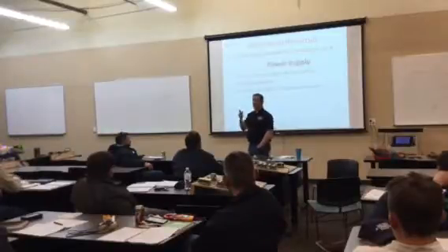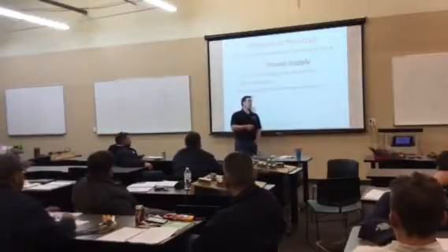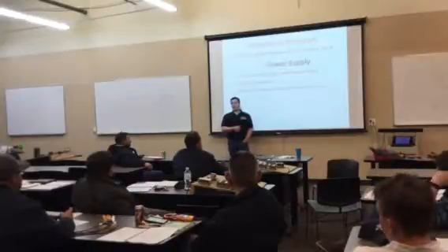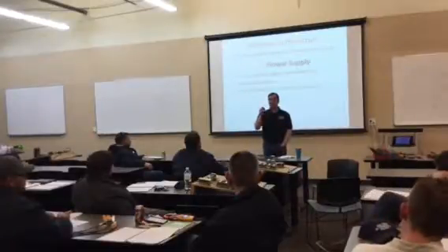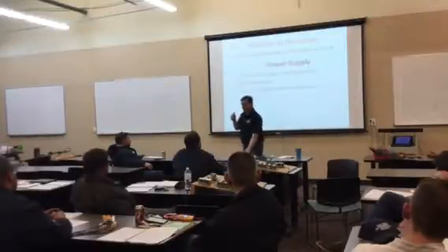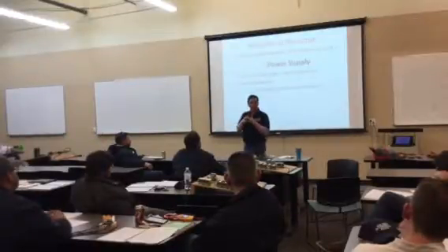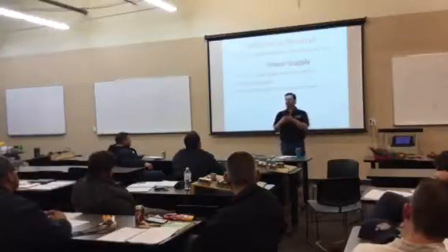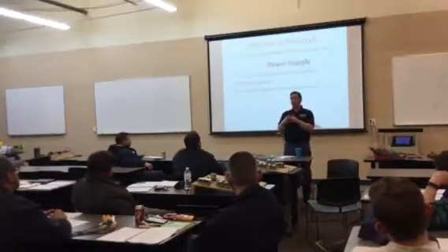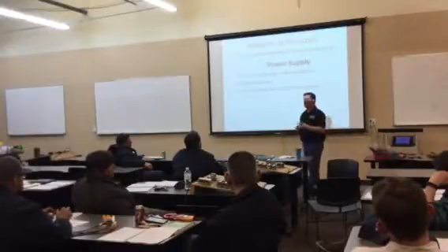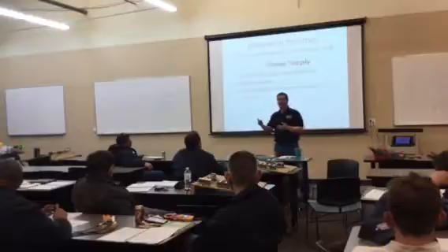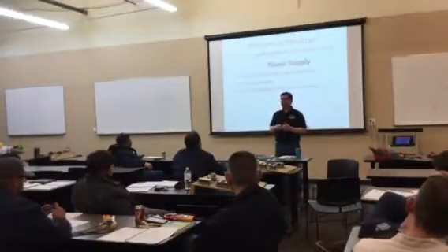So I saw a note up over here about paying attention to FPE breaker panels in homes. Those are older homes, breaker panels made by Federal Pacific Electric. They had an issue on the circuit breakers and the connection points between the breaker and the panel degrading over time. And as the connection point in any electrical circuit is loosened, it's not as tight, that adds resistance to the circuit. So as the electricity passes through that loose connection, that's a point of resistance that generates heat, which leads to a fire, or leads to the whole panel melting down. That's the best case scenario. And that's the reason why you keep your eye out for those FPE panels to change them out.